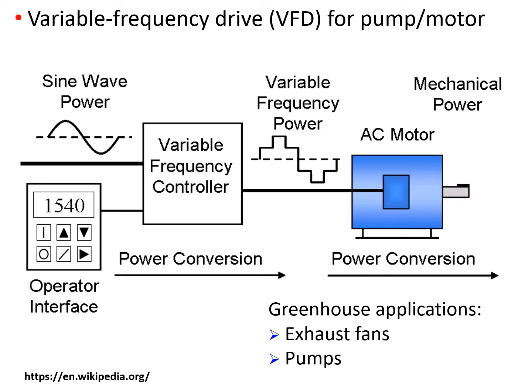Variable frequency drives, or VFDs, are systems that allow an electric motor to be operated at a continuously variable speed. Thus, their speed can be exactly matched with the demand in terms of fan or pump capacity. VFDs increase installation costs, but greatly increase the energy efficiency of fans and pumps.